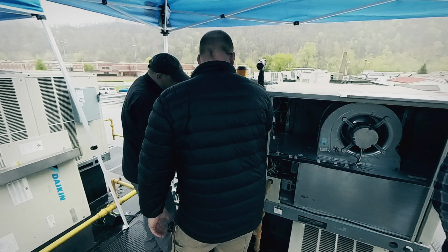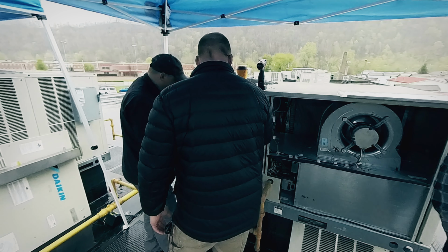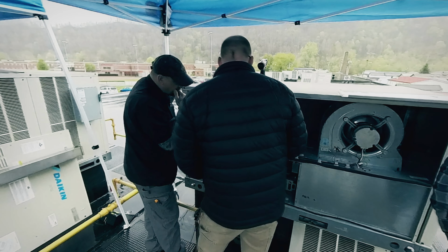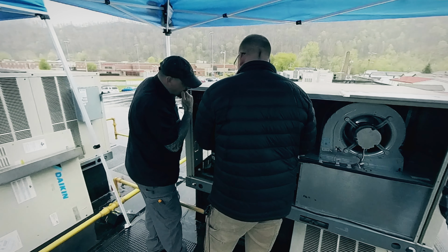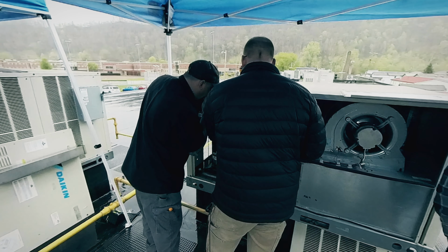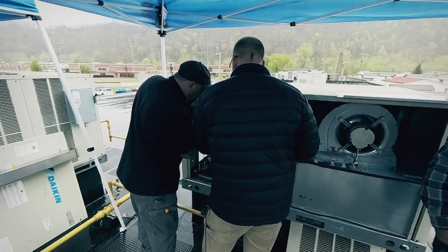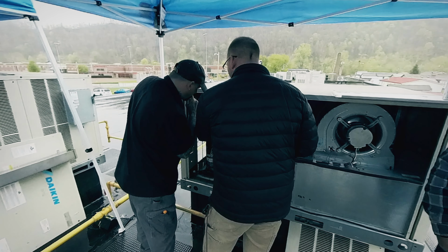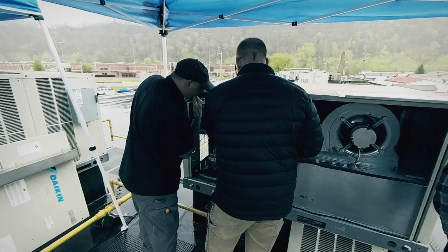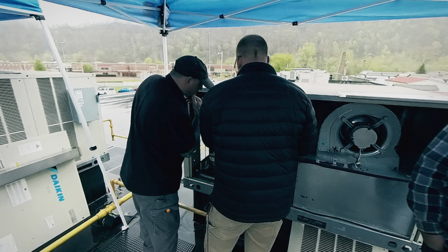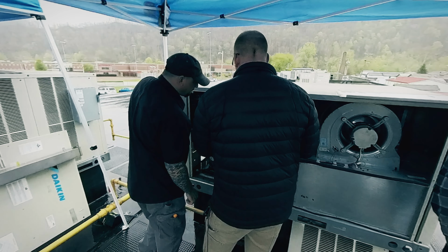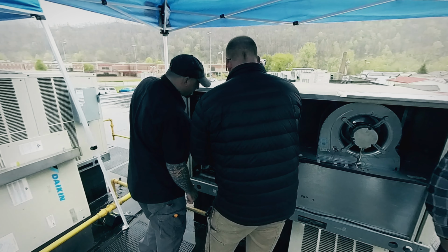Yeah, it's controlled off of this, but like I was telling them, this is your C. If you ever wanted to come up here and work on something, if you had a jumper, you could go from C to G. You see how they're jumped? Your commons go straight to everything, so your ground's already there. All you're doing is throwing 24 volts to each one to bring it on. So you could go from R to G, which is your hot. Not C, R.